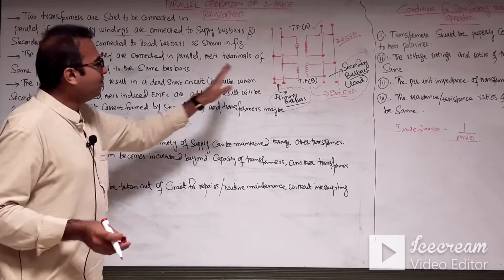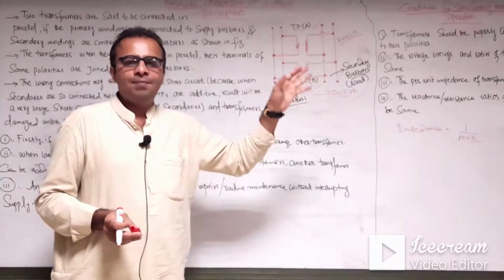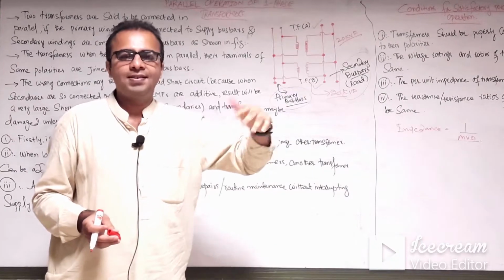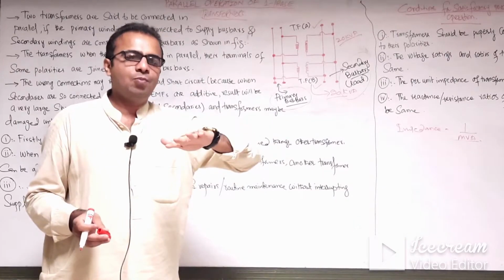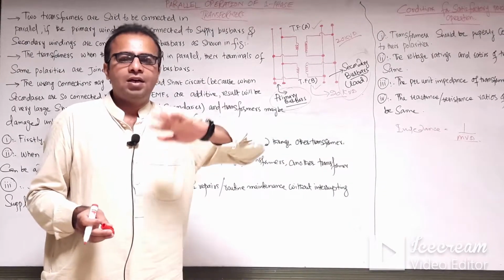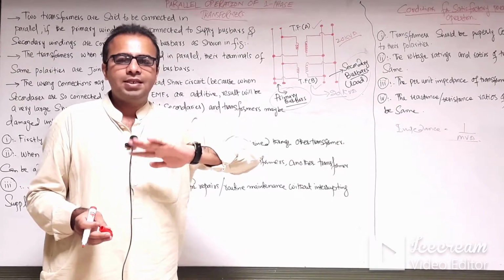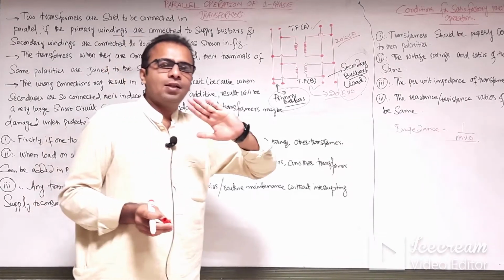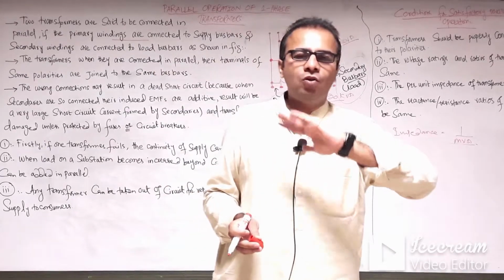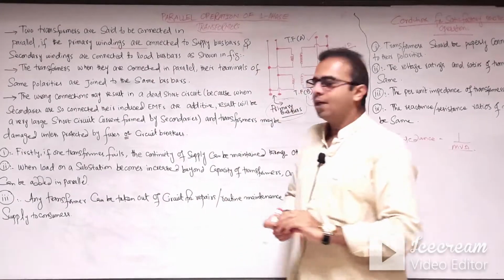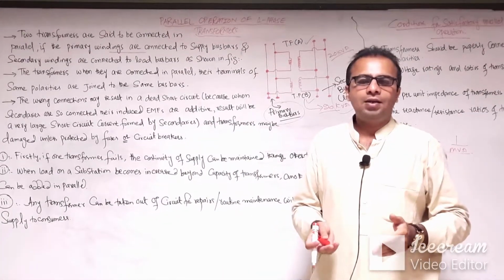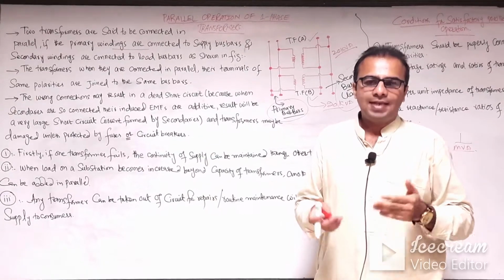Now when the transformers are connected in the same polarity, this will be called the subtractive polarity. In the subtractive polarity or the same polarity, the transformers or electrical machines are under less voltage stress. So the desirable polarity is the same polarity.